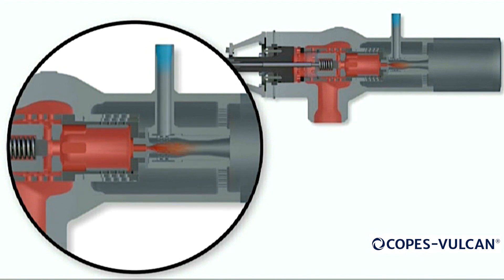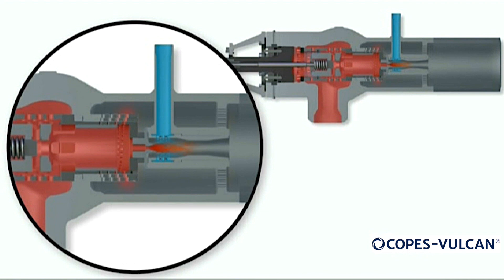The combining tube uniformly directs the cooling water into the atomizing zone. The energy available in the high-pressure steam is efficiently converted into a high-velocity expanding jet of steam. The cooling water is instantaneously atomized and travels forward into the venturi section of the atomizing head.